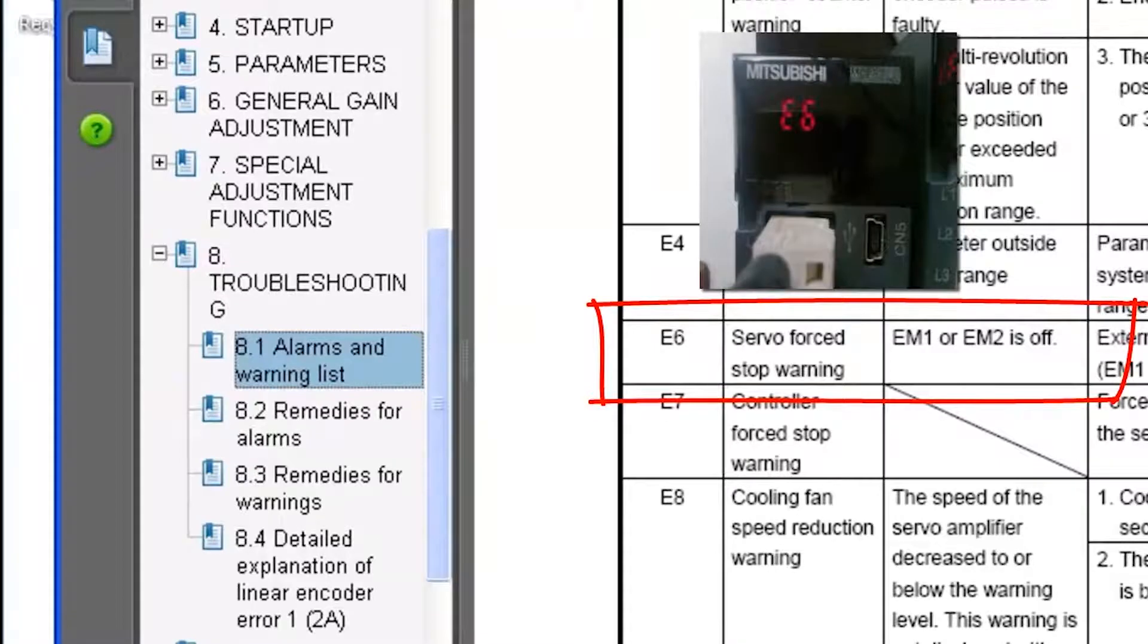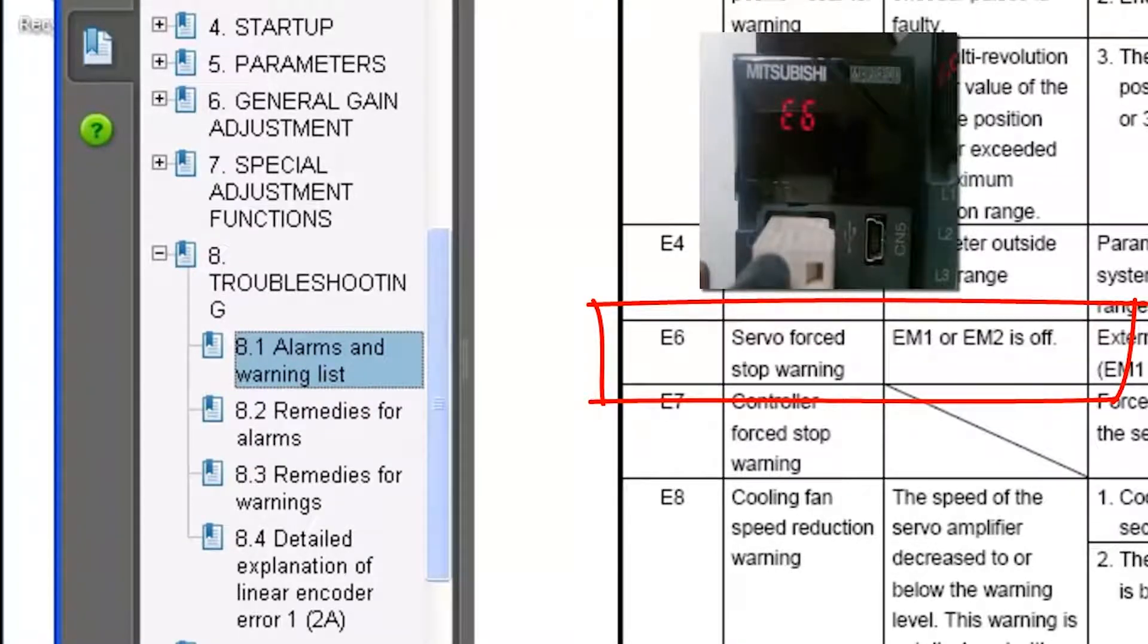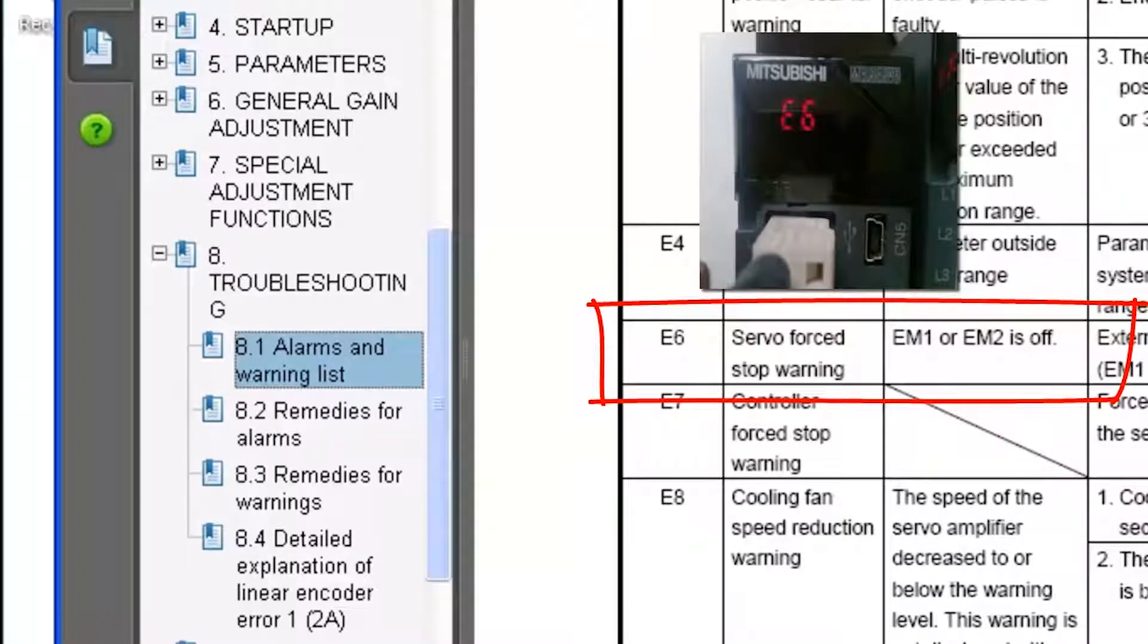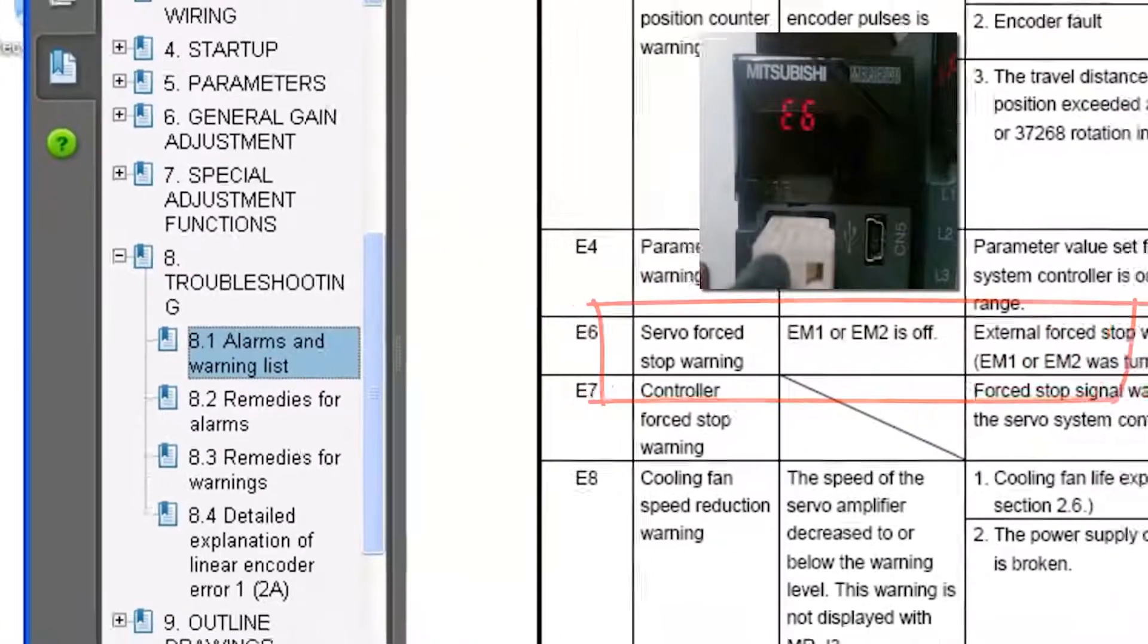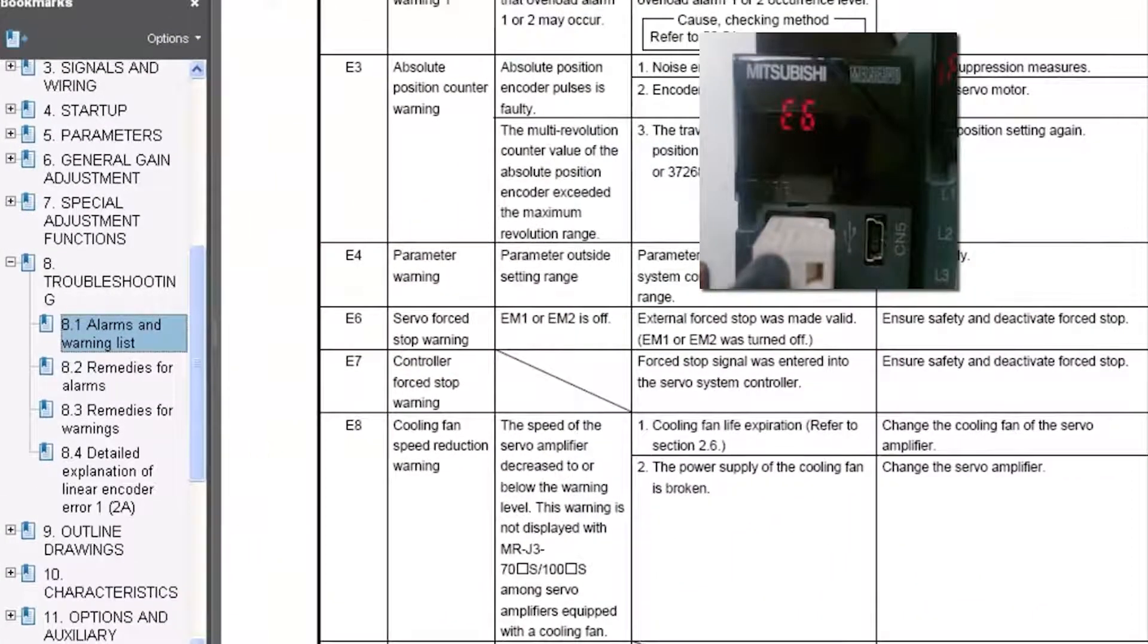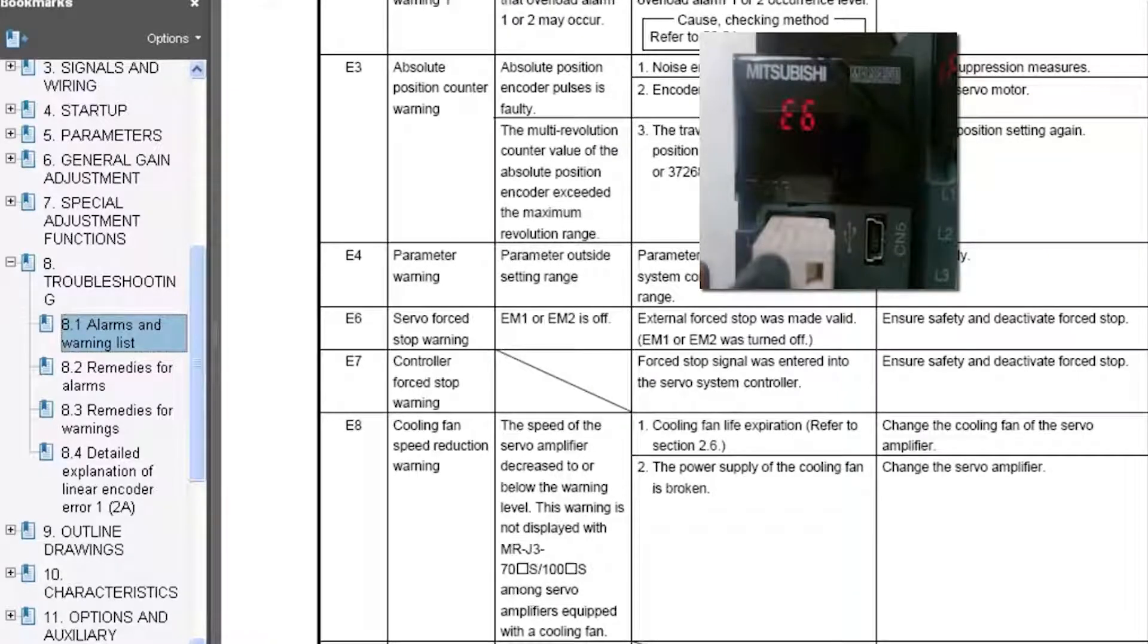According to the MRJ3B safety instruction manual in chapter 8.1, the E6 warning is a servo force stop warning and in order to correct this you need to ensure safety and then deactivate the force stop.